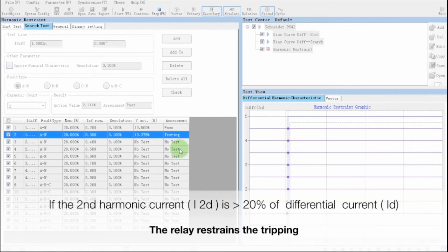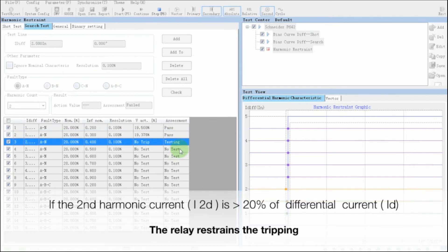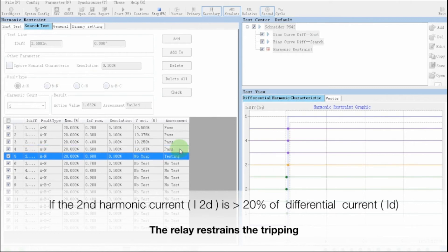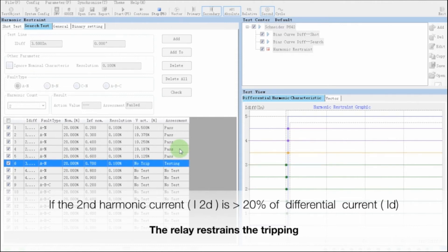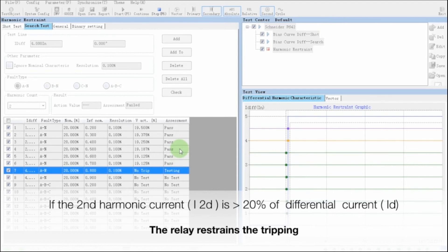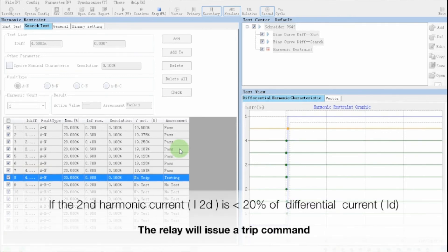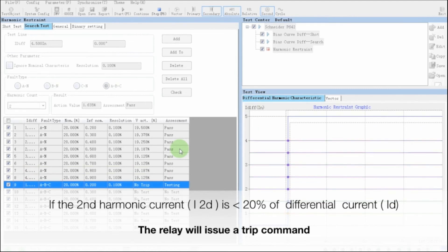The inrush current of transformer, if analyzed, is rich in second harmonic component. So we can use this fact to prevent operation of differential protection. Therefore, the second harmonic restraint is provided in transformer differential protection. Normally, the setting of second harmonic restraint is around 20%. Which means if the second harmonic component in differential relay is more than 20%, the differential relay will not operate. But if the second harmonic component in differential current of relay is less than 20%, the differential protection relay will operate.